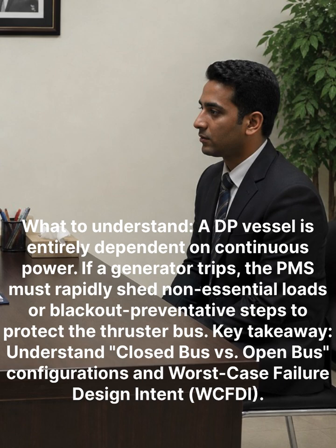What to understand? A DP vessel is entirely dependent on continuous power. If a generator trips, the PMS must rapidly shed non-essential loads or take blackout preventative steps to protect the thruster bus. Key takeaway: understand closed bus versus open bus configurations and worst-case failure design intent, WCFDI.